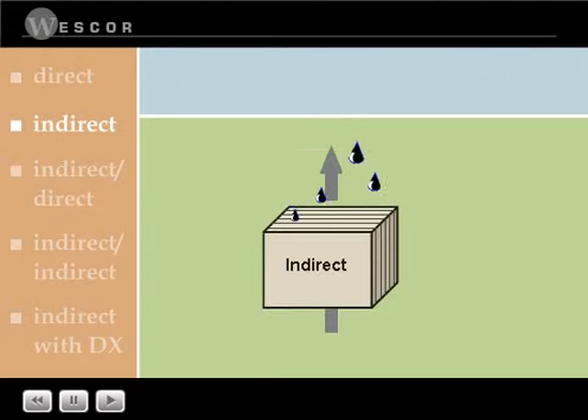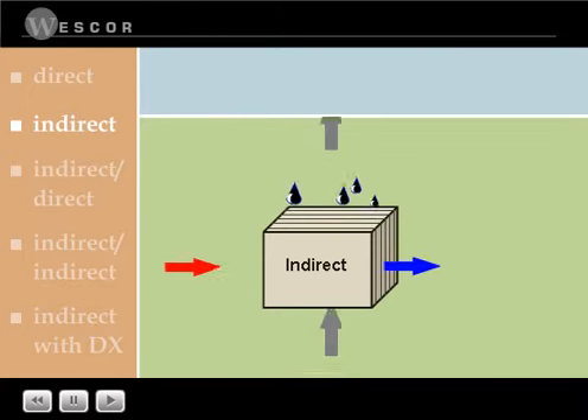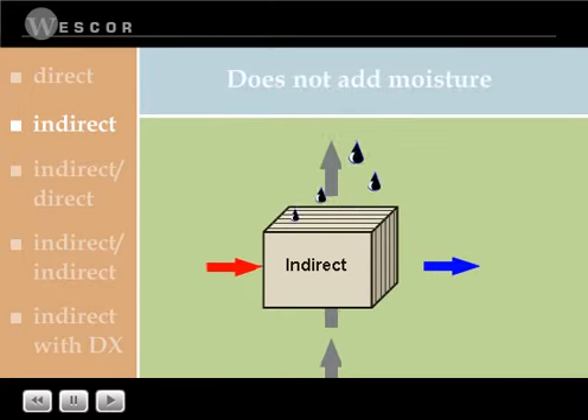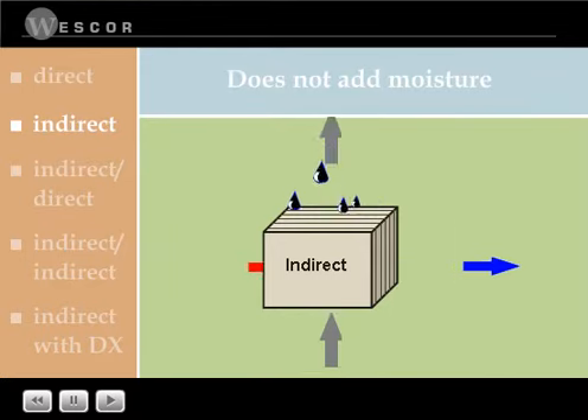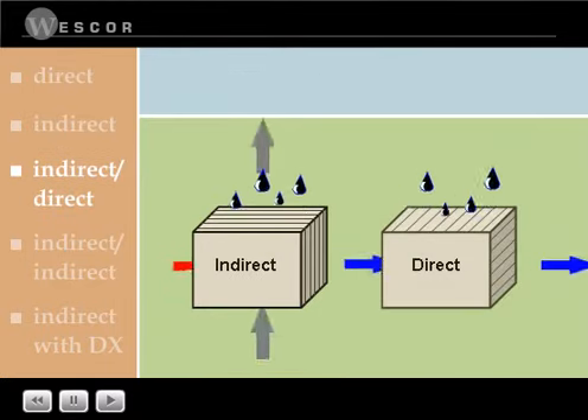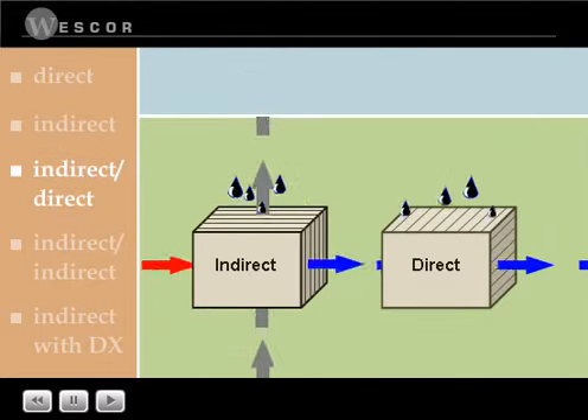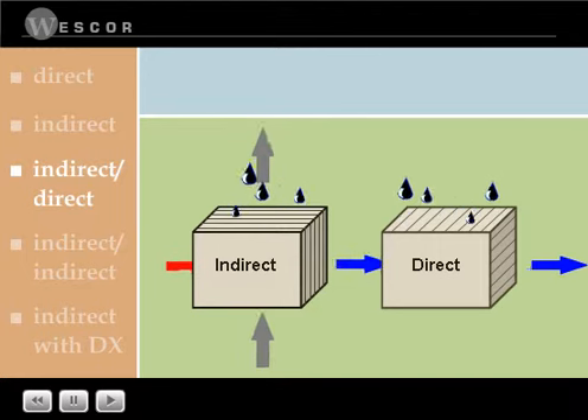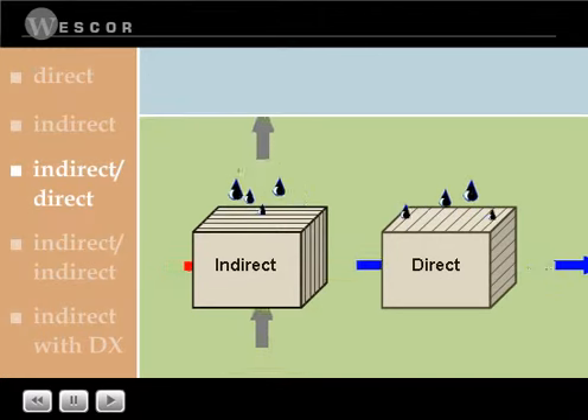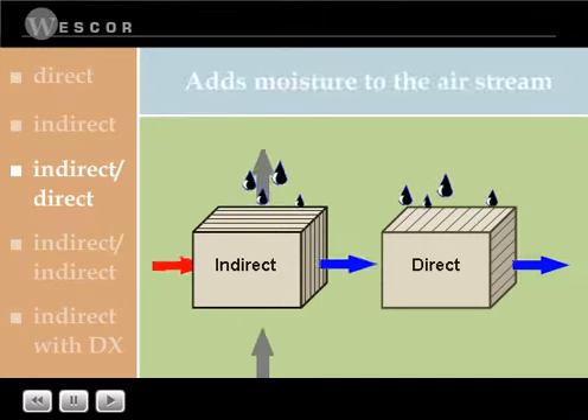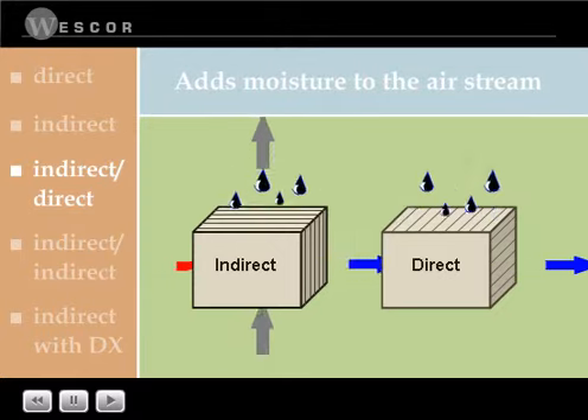With indirect evaporative cooling, a secondary airstream is cooled by water. The cooled secondary airstream goes through a heat exchanger, where it cools the primary airstream. Indirect evaporative cooling does not add moisture to the primary airstream. With indirect-direct evaporative cooling, the primary airstream is cooled with indirect evaporative cooling, and then cooled further with direct evaporative cooling. Moisture is added to the primary airstream.